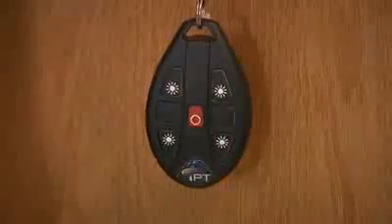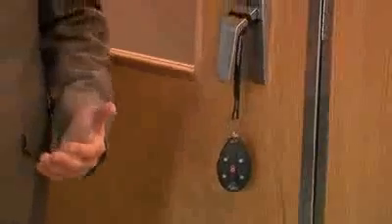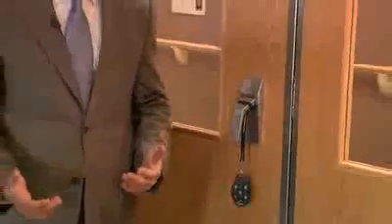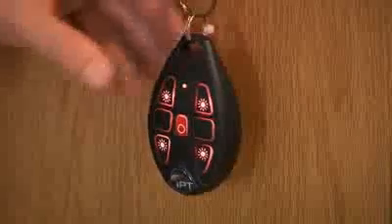Because the IRS 3200M creates a very powerful UVC field, it's important to protect human beings from entering the room. The IRS 3200M employs a safety feature which monitors the door for entry. This system looks for motion. When the device is activated, it's required that this motion sensor is activated, so that if somebody enters the room, the device will shut down immediately.